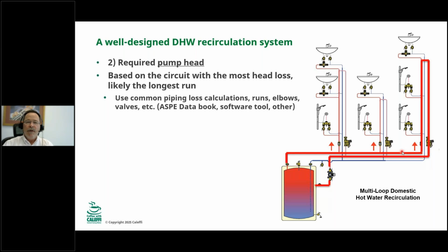So that's where you need to use your standard piping loss calculations with the runs and the elbows and the isolation valves and the balancing valves too. You need to account for everything that causes head loss in that circuit. The balancing valves are part of that circuit.